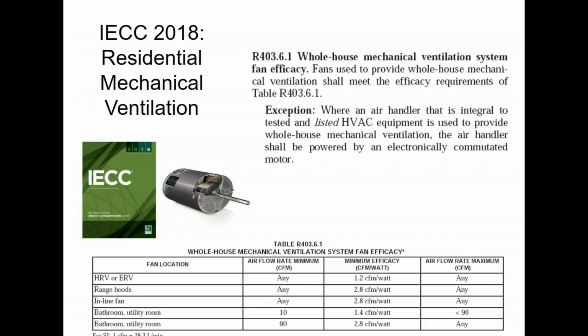The way the code is written, the answer would be yes, you would have to do that. Now, the way it's been enforced, where I live in Illinois, is the inspectors are not enforcing that. Right or wrong, they're just not doing that. Probably because they think it's pretty impractical, depending on the location of the furnace. New construction, absolutely no-brainer. A gut rehab, absolutely no-brainer. On a furnace change-out, your inspector probably won't make you do it, but you should be doing it per the letter of the law of the code. If you know that they just sealed the house up as well and made it tight, you definitely want to find a way to do it. Otherwise, people are going to have problems in general. So hopefully that answers your question, John. So if you're using the furnace or other air handler, it's got to have an ECM motor.